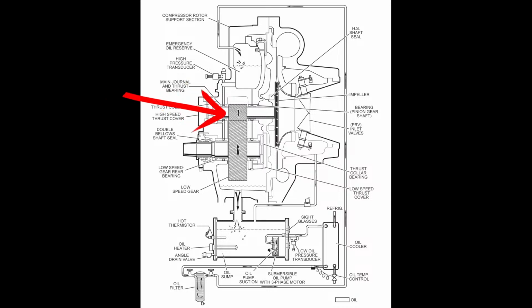So we have our high-speed shaft here for the YK. This is directly attached to your impeller. You have a bull and pinion gear. So it's your pinion, this is your bull, helical gears, step and speed up, motor shaft here. These also have thrust collars on them as well, or technically the thrust collar is over here. And then our high-speed thrust collar is here. And then the high-speed thrust bearings, I'm sorry, right here is the collar, right here is the bearings.